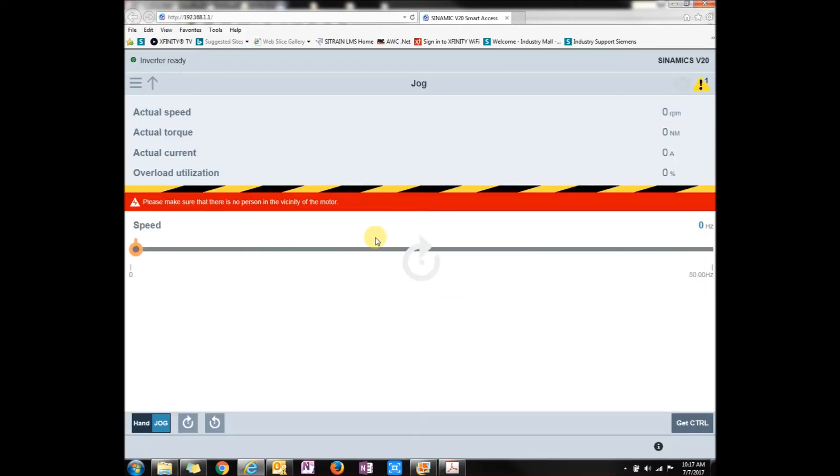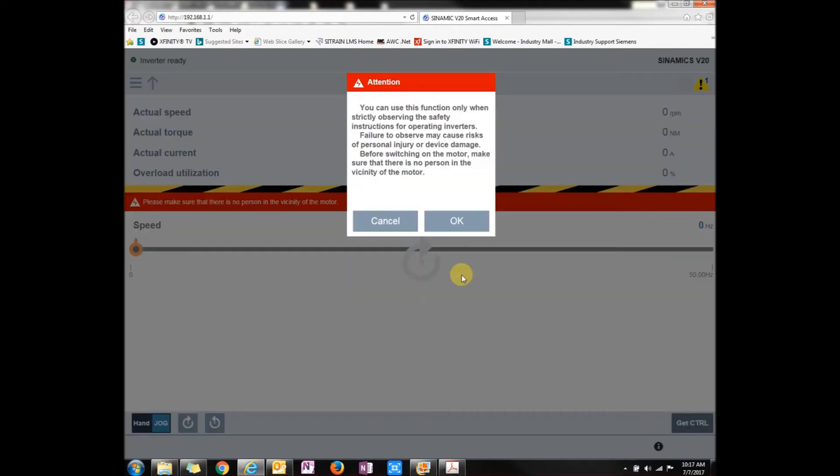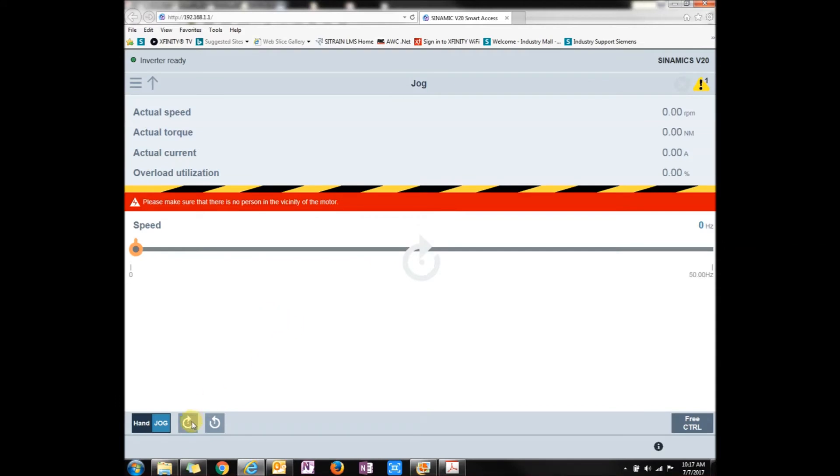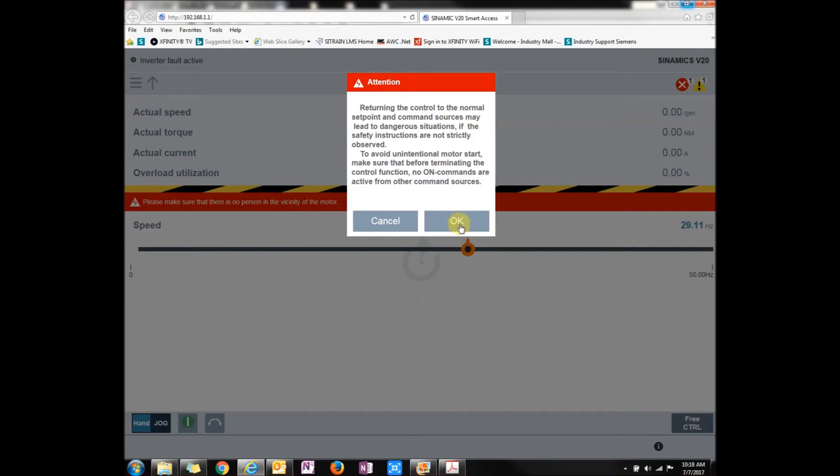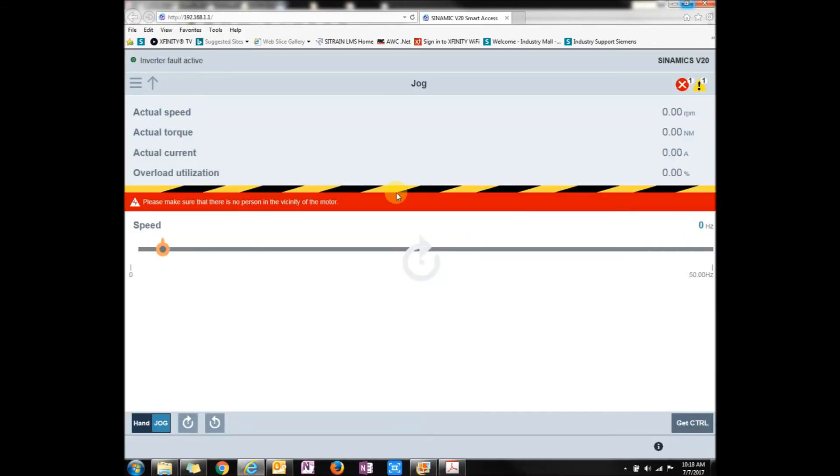This is how you can control the drive via your phone or your PC. The only problem with this is when you're in this screen, when you do press get control, this makes it take over how it's going to be controlled. So you're not going to be able to control it from your push button. It's only from whatever you're connected to with the Wi-Fi. So right now I can press hand, and if I press start, it'll try to run. Then there will be a fault because I don't have the right voltage. But right now I can't get out of here since I have control. So I can click all I want, but I'm not going to be able to get out. I need to stop this motor and then free up the control. That's a good thing. It makes you stop before you can get out of the screen.